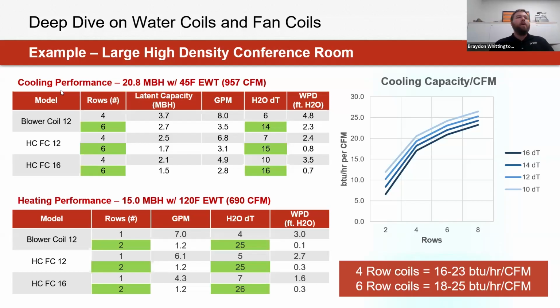And making sure that when we're adjusting these rows, as we know in the background, there are also some parameters happening with our circuits and other construction of how deep it is, that it's not having an influence on other concerns, such as our fluid pressure drop, as well as our air pressure drop coming from the coil itself. And what we're seeing when plotting it out is that across the board, at least for this case, because we are dealing with lower temperatures, a bit bigger of a coil is more beneficial for trying to achieve those waterside delta targets for the MBHs that are currently listed. Because we learned that bumping up that initial row of coil is going to maximize the first potential gain of capacity that we're going to be yielding from that coil.